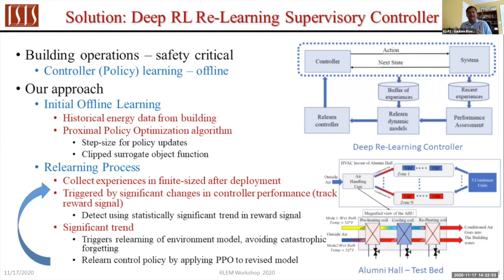In the building we work in, we do centralized supervisory control, controlling the discharge temperature and humidity from the air handling units. They operate in two modes: when it's cold, the system just heats the air, but when it's warm and humid, it cools down the air and then reheats it back to a comfortable temperature before discharging it. We honor both of these modes, and our controller operates very well in both.